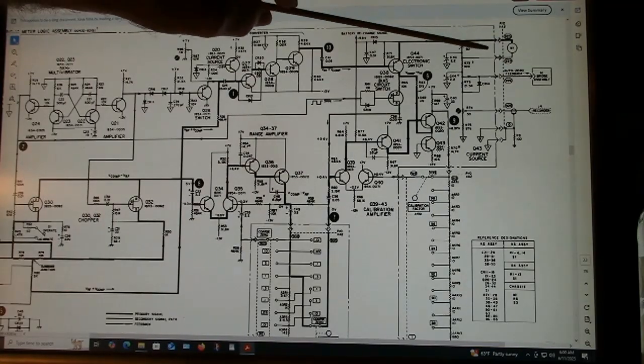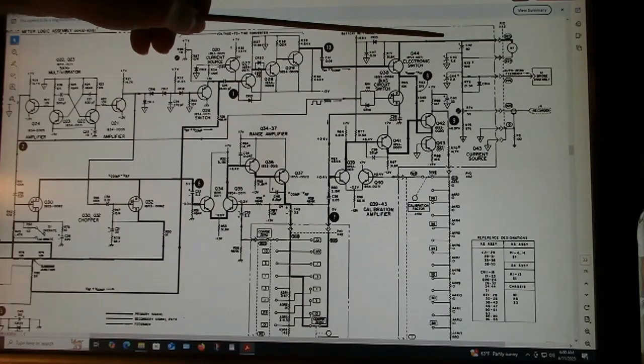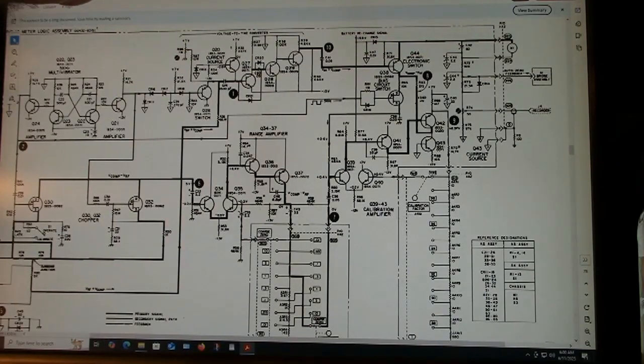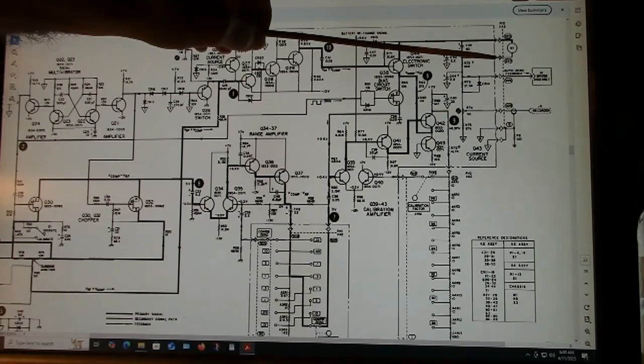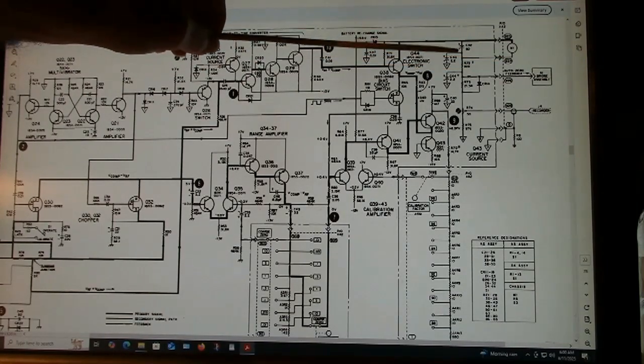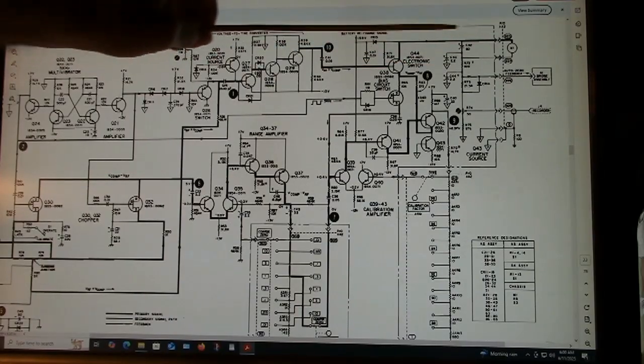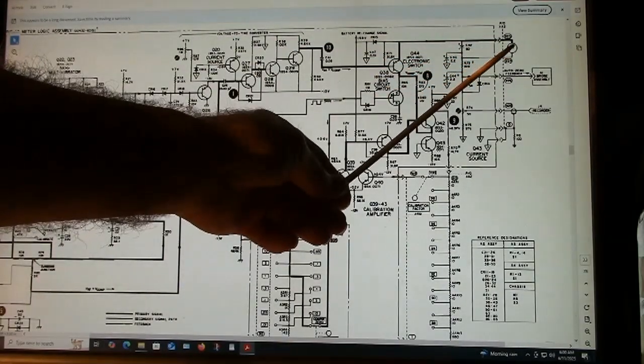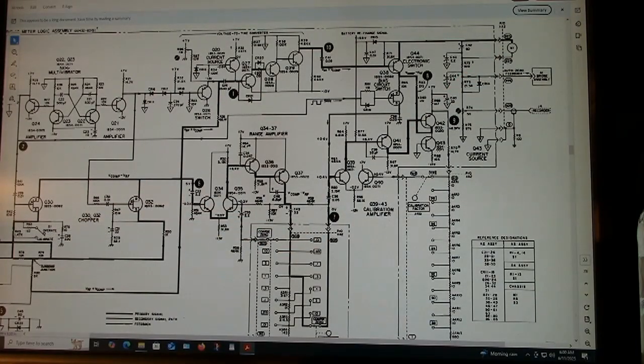And then on the right side, at the upper right, that signal is fed to the meter, which is calibrated in power. You've got a capacitor across it which integrates those pulses to feed the meter here, M1. So it's interesting, the purpose of all of this discrete circuitry is to provide a stable output in the meter that only varies with RF input to the device. It doesn't vary with ambient temperature changes.